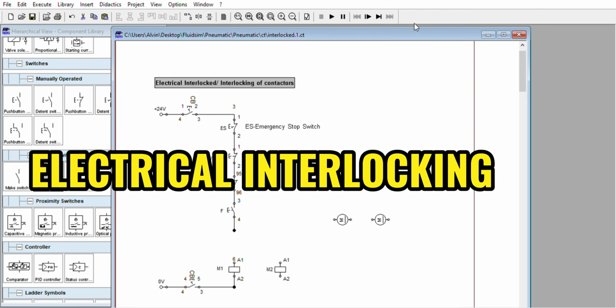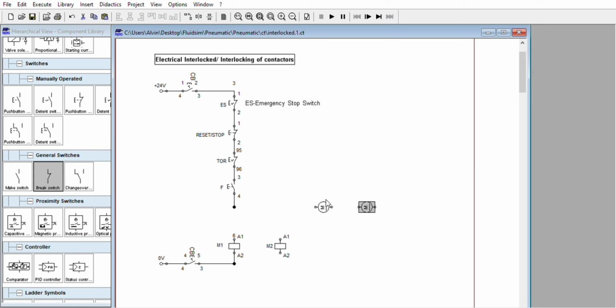Interlocking of contactors. As we know, electrical interlock is to prevent the other contactor or other motor from functioning if the first one is starting or running. Say for example, you can start at any motor, let's say motor 1 or motor number 2. If you are starting motor number 1, you cannot start motor number 2 because it is interlocked by motor number 1. So you are going to de-energize motor number 1 first, so you can start motor number 2.